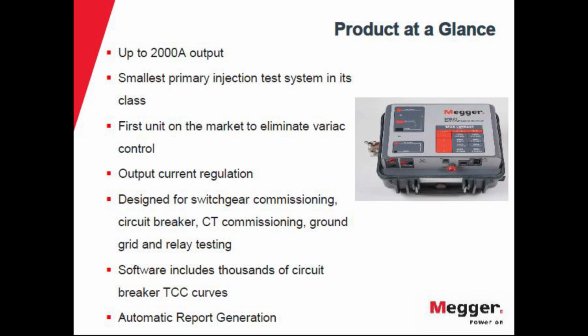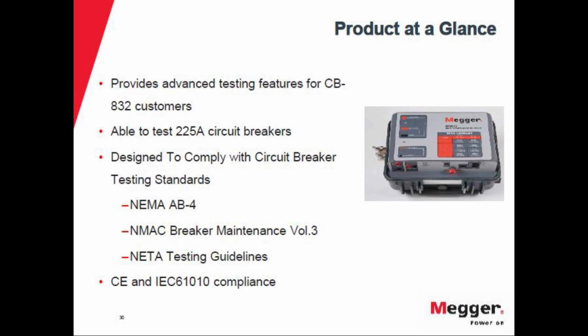It's also the very first unit in the market to eliminate the variac. As you can see, there's nothing on the unit to control it. Everything is controlled from a computer, and the unit does the automatic regulation and control of the current for the test. It is designed for switchgear and circuit breaker commissioning. You can even do CT commissioning. These 2000 amps are instantaneous, but the unit can do 500 amps continuous output. The highest breaker you can test with one unit is 225 amps.